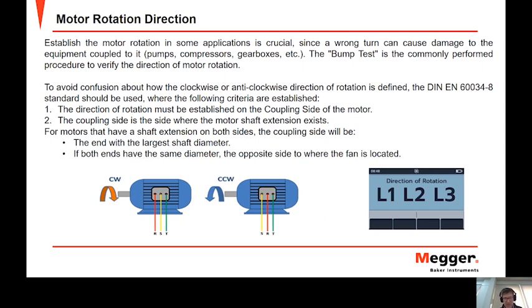And motor direction of rotation is defined by an international standard, IEC 60034-8, where the following criteria are established. So the direction of rotation must be established on the coupling side of the motor. The coupling side is where the shaft extension exits from the motor. And for motors that have a shaft extension on both sides, then it's generally the end with the largest diameter. And if the 2 shafts both have the same diameter, then it's the opposite end from the fan.